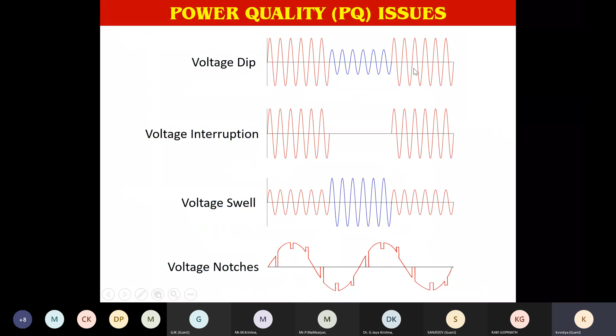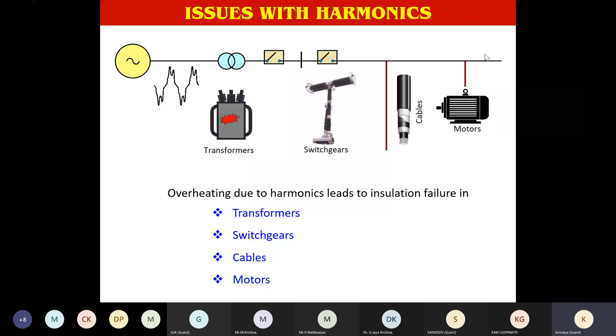Because power electronic devices are non-linear devices, they create a lot of issues like voltage variation by way of dip or interruption or swell or notch, etc. Then almost all the equipment in that electrical system, especially electromagnetic devices, transformers, all those will be getting affected because of the high frequency third harmonic, fifth harmonic, all those unwanted signals. So there will be frequent failures of some of the equipment if you are not taking care of these harmonics.